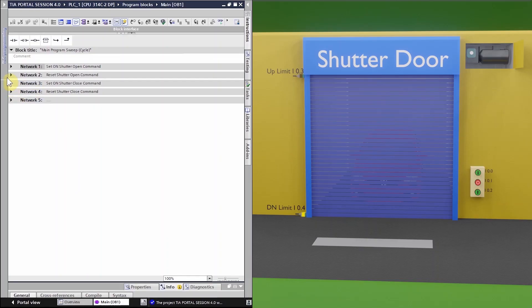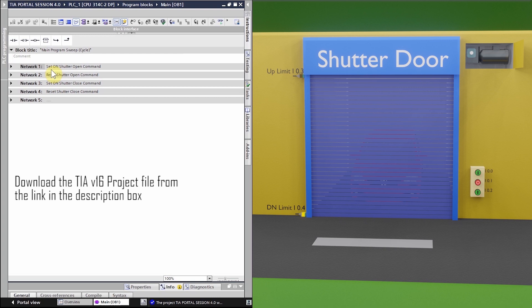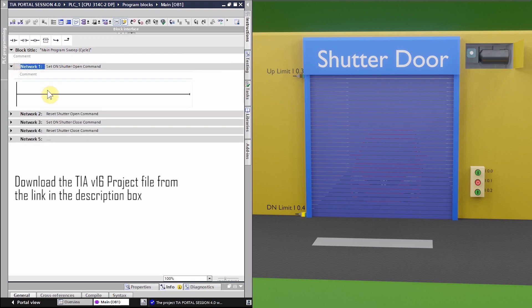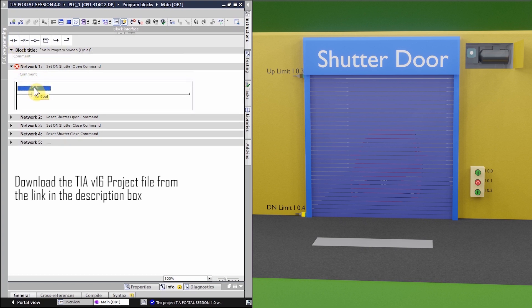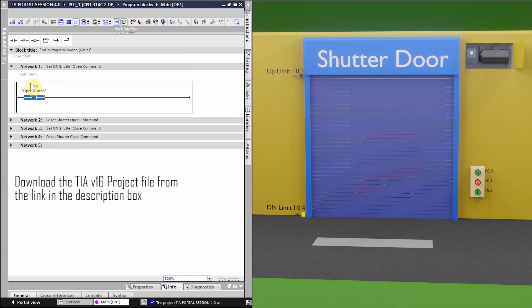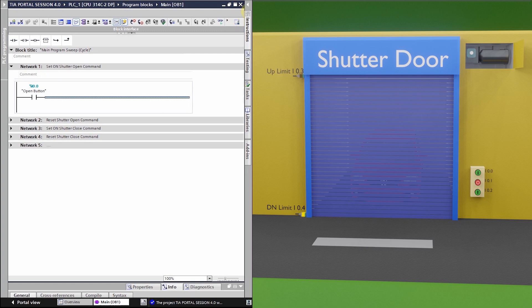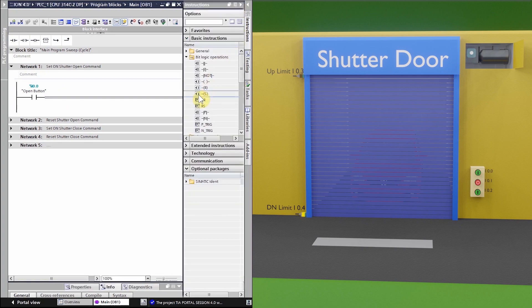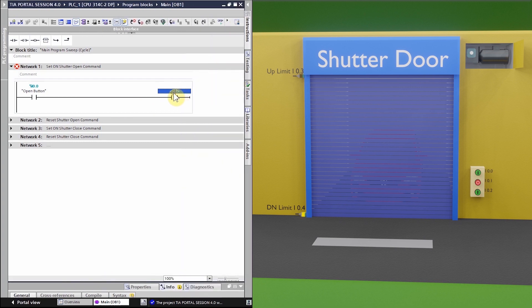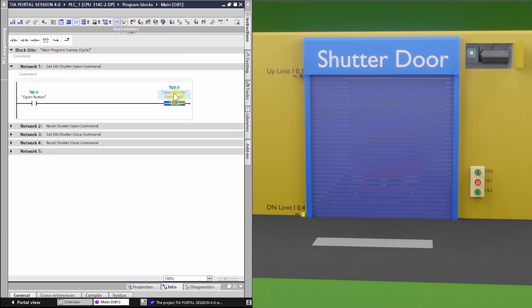In network number one we have the logic to set on the shutter open command. We insert a normally open contact of push button I0.0, which is our open button. Whenever we press the open button, it should set our output Q0.0. We use the Set Output command, dragging and dropping it onto the ladder logic and specifying Q0.0. So whenever we press I0.0, it sets output Q0.0 and the shutter starts to open.